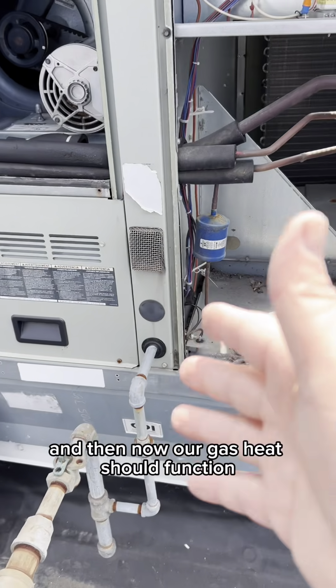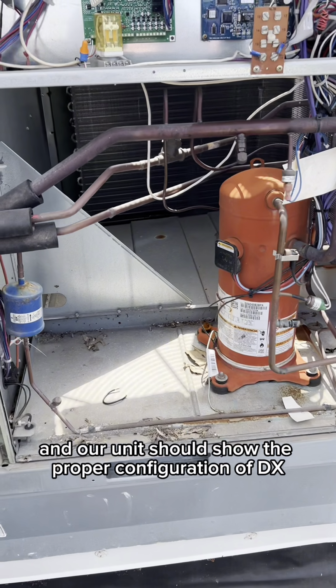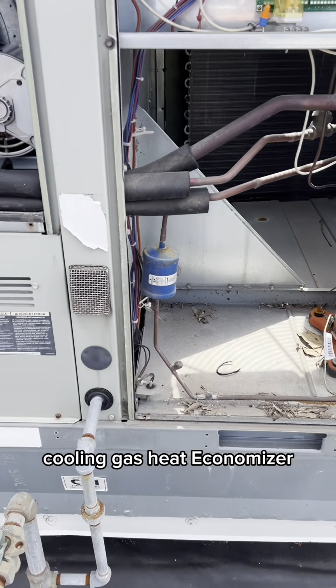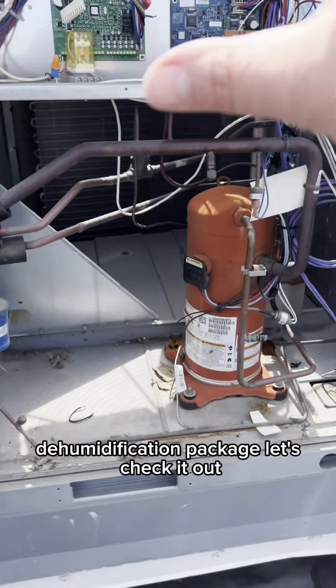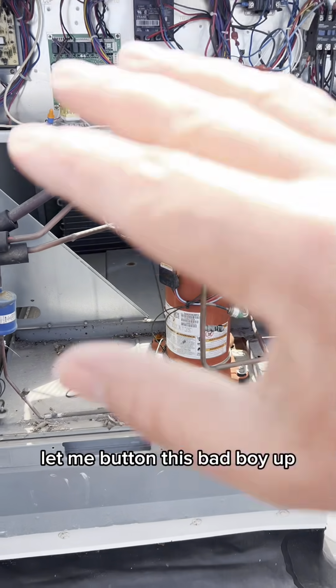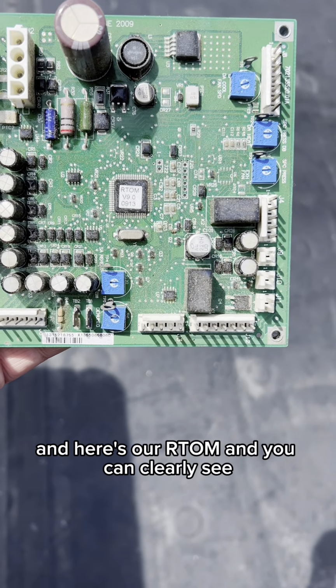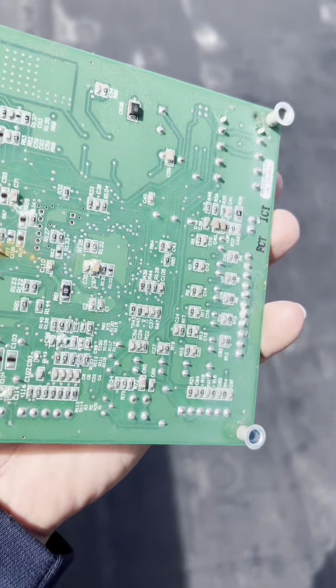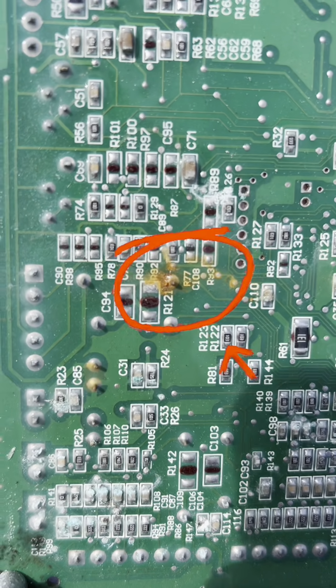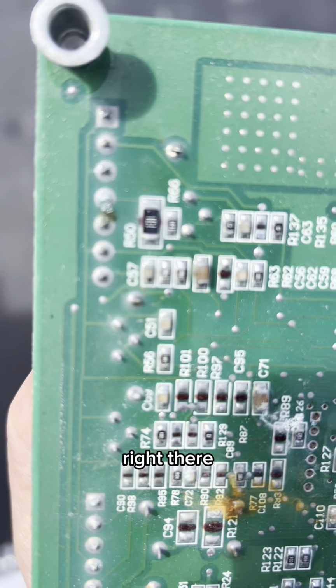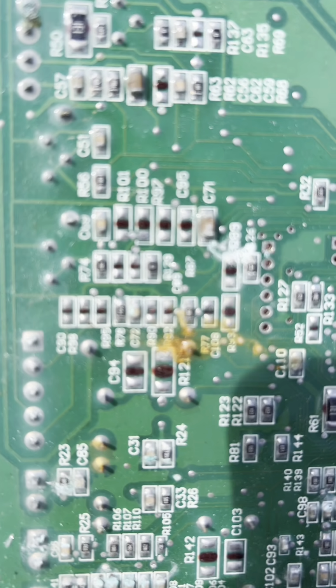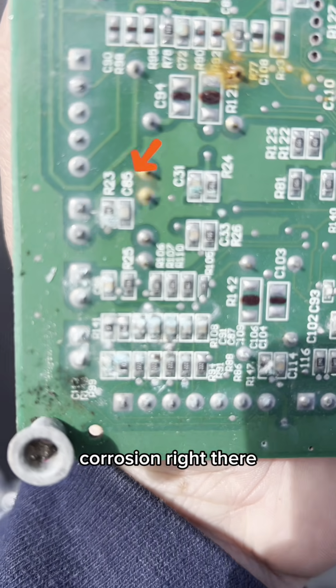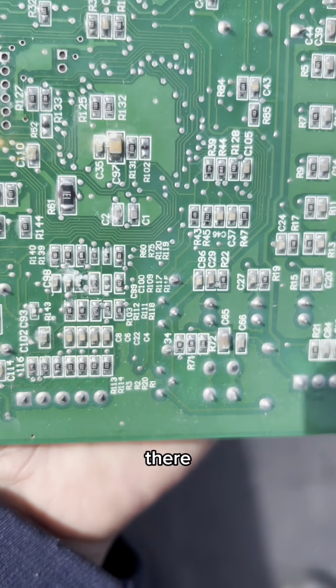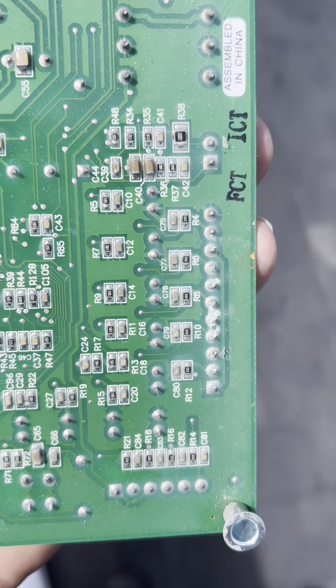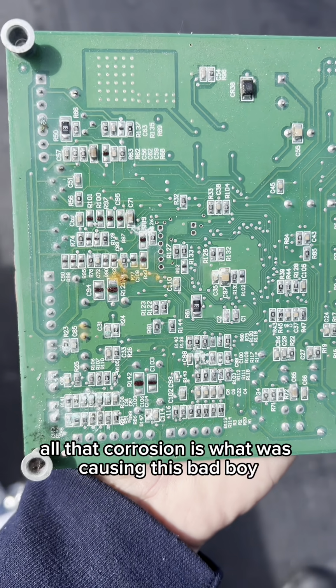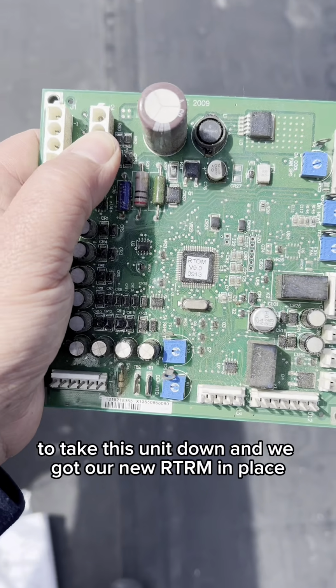And then now our gas heat should function, and our unit should show the proper configuration of DX cooling, gas heat, economizer, dehumidification package. Let's check it out. Let me button this bad boy up. And here's our RTRM, and you can clearly see the problem. Right there. Corrosion right there. So all that corrosion is what was causing this bad boy to take this unit down.